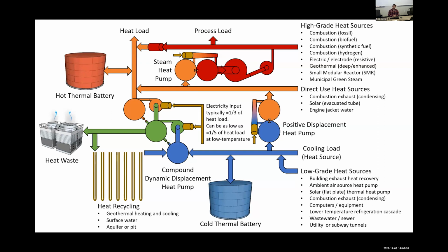It is a challenge, like at UC Davis, where there's an existing steam distribution system. You don't have a network in which to do central heat pumps distributing hot water to buildings. But that's some of the work that's been going on to put that system into place. And it's being done when the steam system would have needed replacement anyway. So some of the steam system was at the end of its life, and it's being replaced with hot water so that the campus can take advantage of the efficiency gains that you get by generating hot water with a lower temperature heat pump.